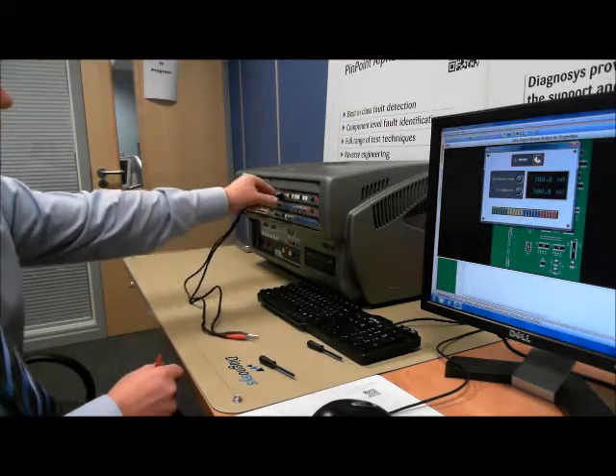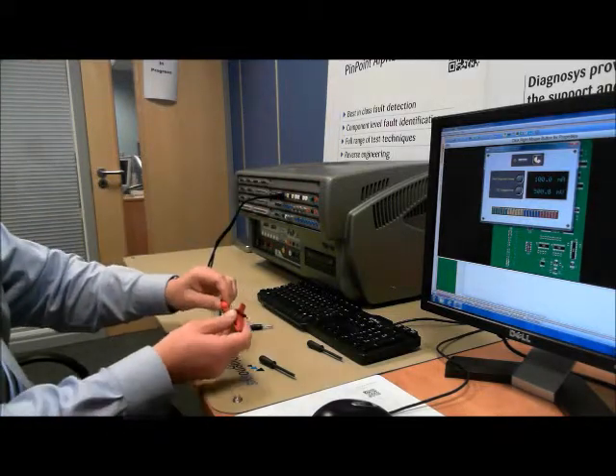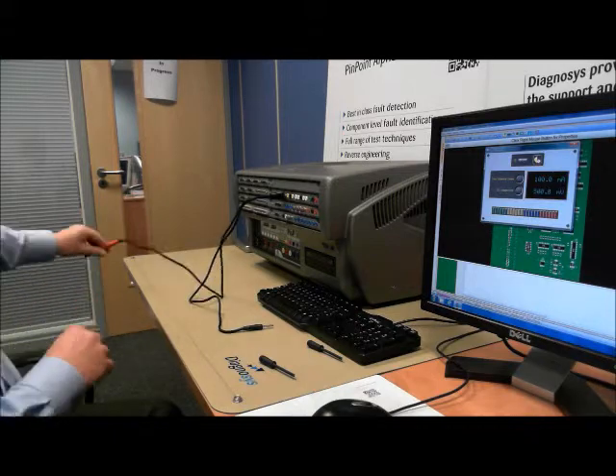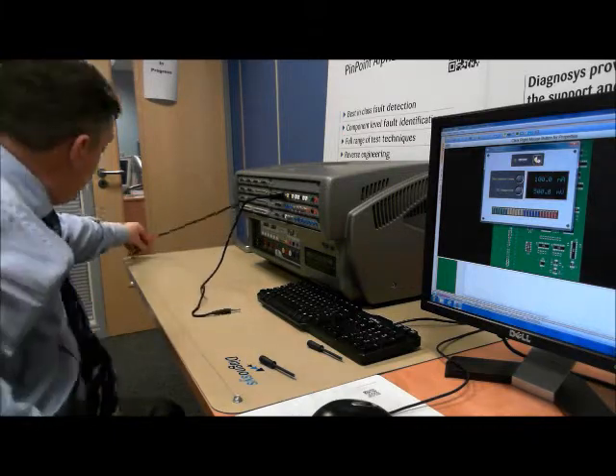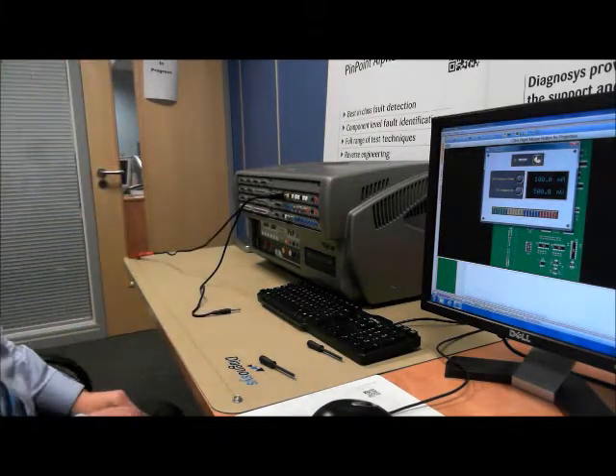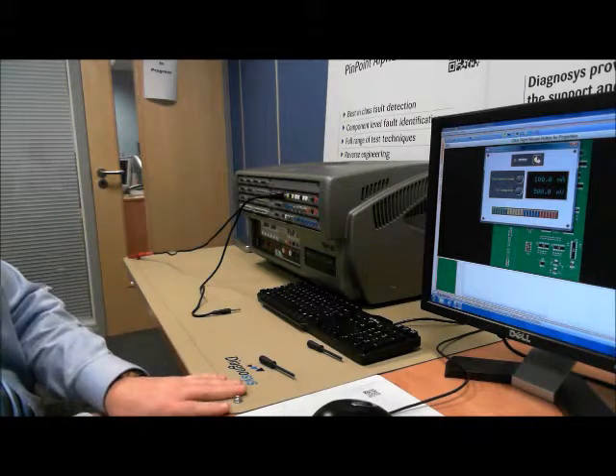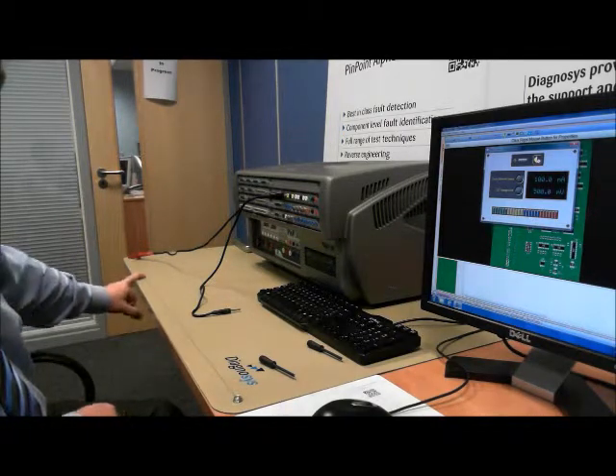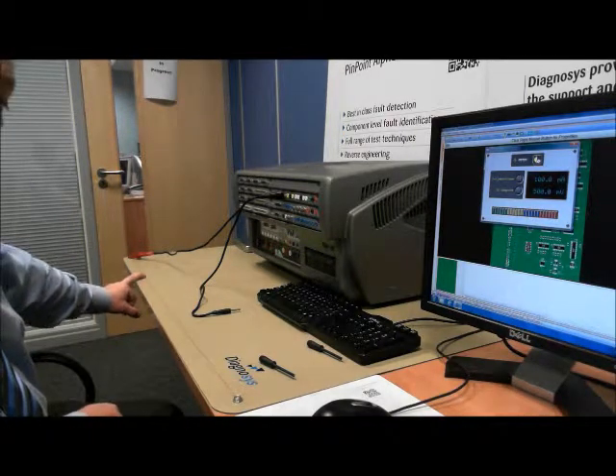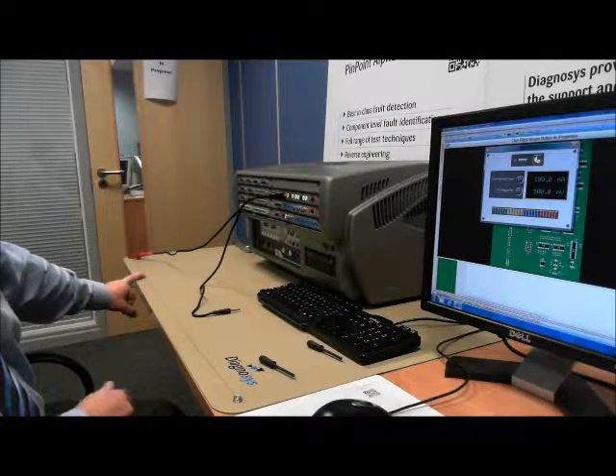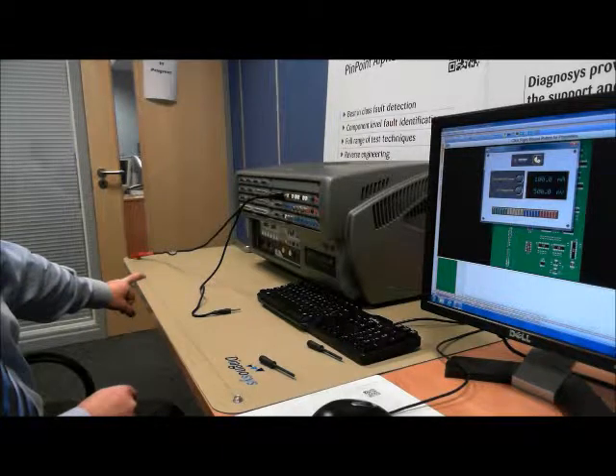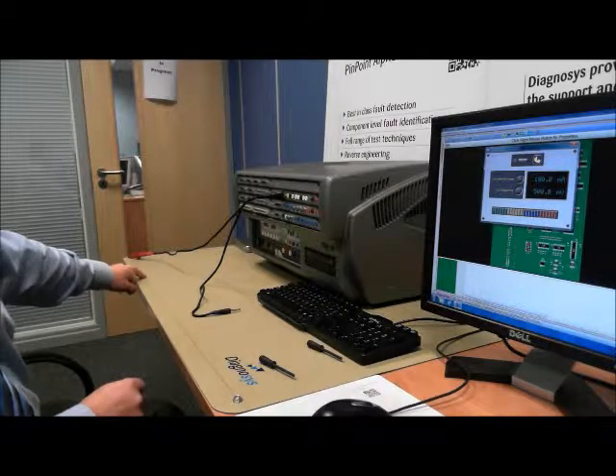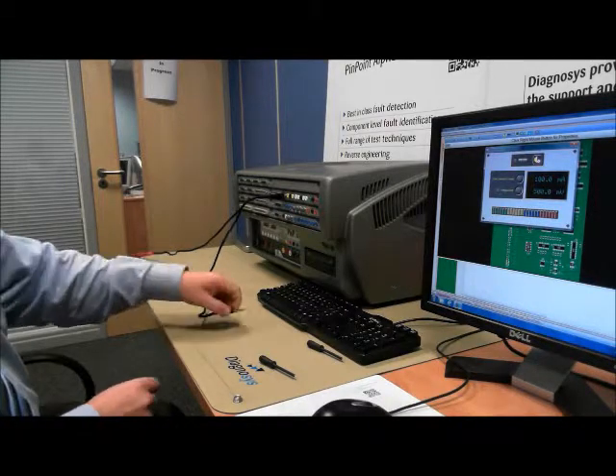We connect the shorts locator lead up to the pin point, connect the crocodile clip output to one end of the shorts locator leads and connect that to one of the studs. We will then simply move along the thin copper wire towards the second probe. As we get closer to the other end, the audio output frequency is going to increase as the resistance drops.